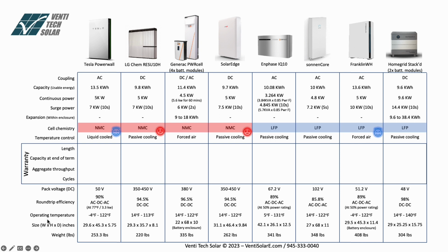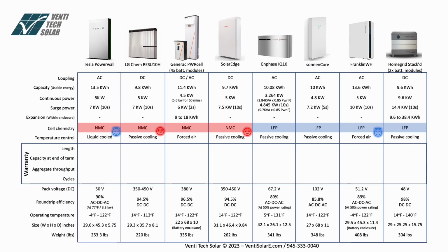Now, operating temperature is one of the factors that is very important. And here is where you can see the tug of war between the engineering developing a product and the marketing and the sales team trying to create a product that's stacking against other products and other manufacturers. So, for example, a technology with NMC, I would expect to have this kind of range for working environment, from -4 Fahrenheit to 122, and they can do that because it's liquid cooled, so they can control the high end of the battery cells, the high end of the temperature range.